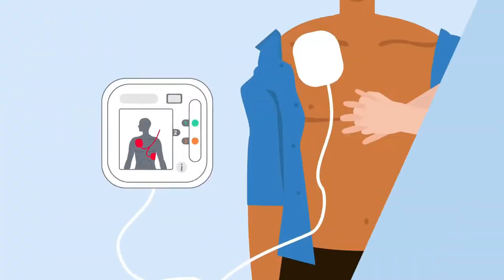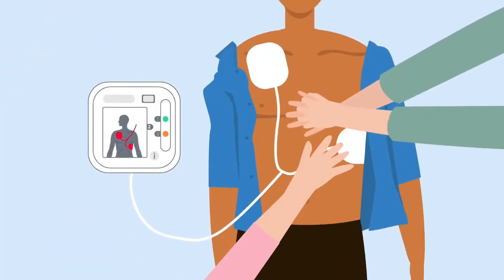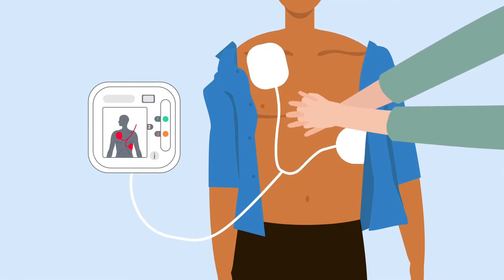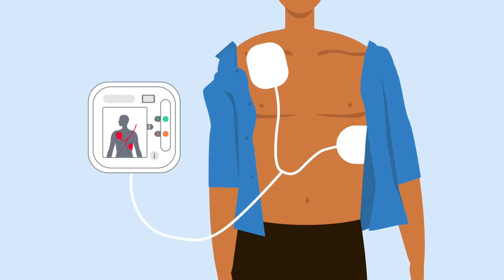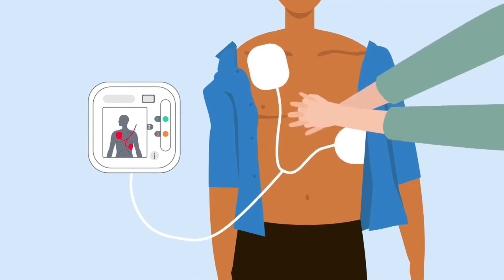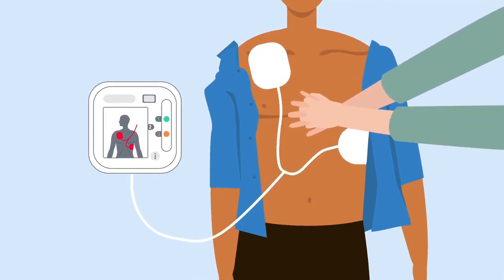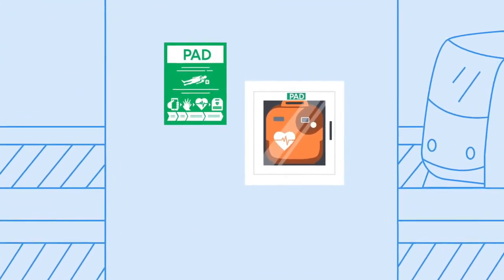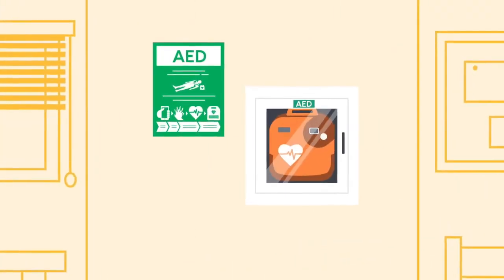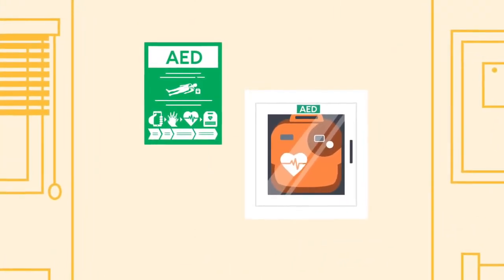AEDs can be semi-automated or fully automated. Semi-automated defibrillators analyse the heart's rhythm, and if an abnormal heart rhythm is detected that requires a shock, the device prompts the user to press a button to deliver a defibrillation shock. Fully automated defibrillators analyse the heart's rhythm and deliver a defibrillation shock if commanded by the device software without user intervention.